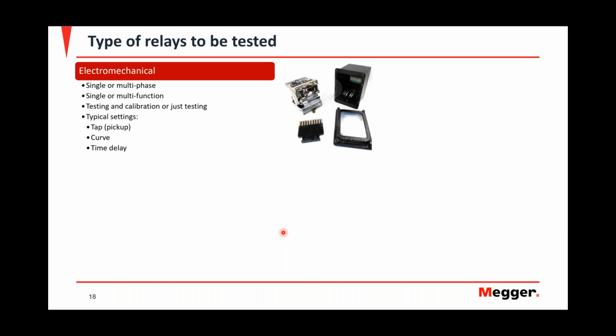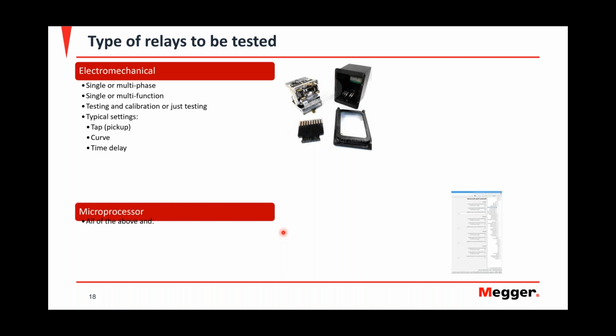Things to keep in mind when you're testing an electromechanical relay, everything from a preparation perspective: is this a single or a multi-phase relay? A single or a multi-function? Am I only doing testing but not calibration? I personally have done a lot of testing on electromechanical relays, but I have not done any calibration. I try to stay away from that because it's a science on its own once you start tinkering with the relays. So it's good to know what your responsibility is. Typical things that you would check on a 50/51, which is probably the great majority of the relays out there: you're going to check your tap setting, which is your pickup, the curve that it's using, and the time delay on it.